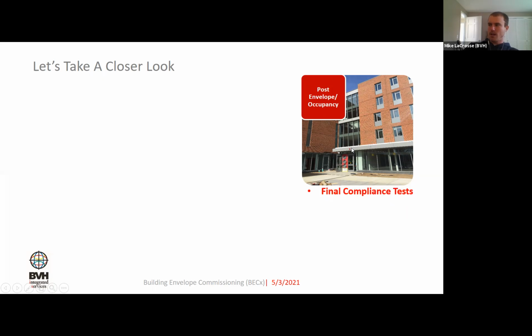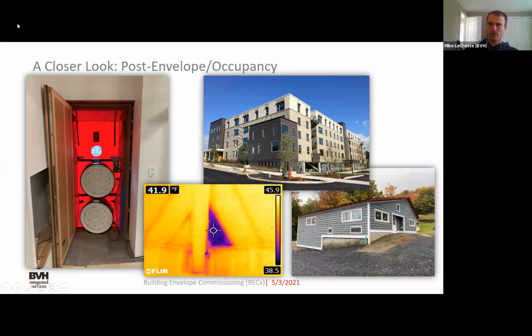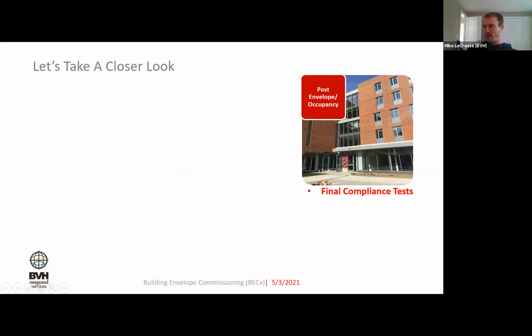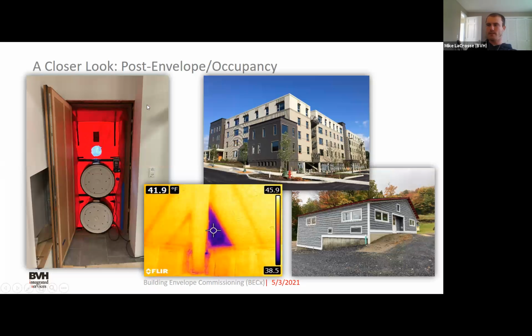So we do that through a blower door test. Here's an example setup, you may have seen this before. Typically this is where we go to 50 pascals of pressure. In fact, for this Pondside 4 building, it was tall enough that we actually went to 75 pascals of pressure. The reason we did that is when you get into tall buildings, stack effect can be greater, so to overcome that stronger stack effect, we'll sometimes go to a higher pressure. Typically, it's 50 pascals.